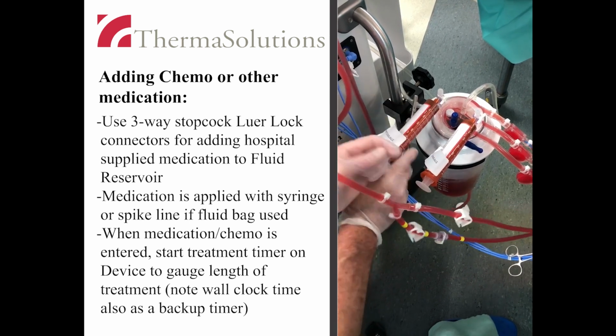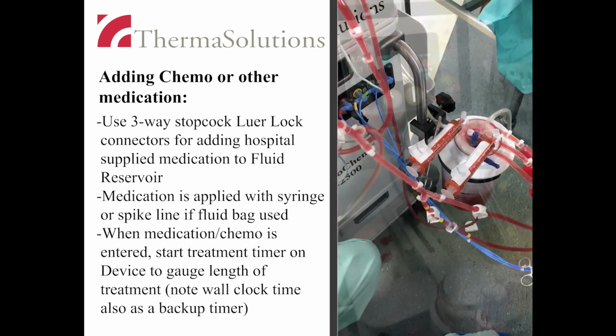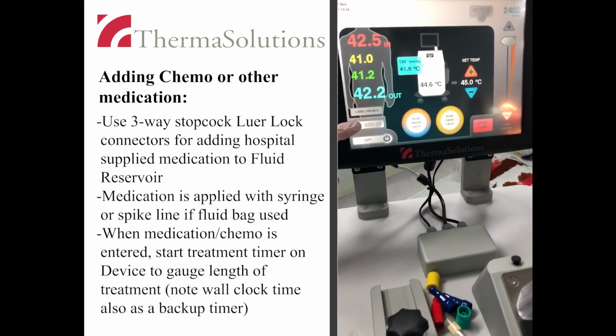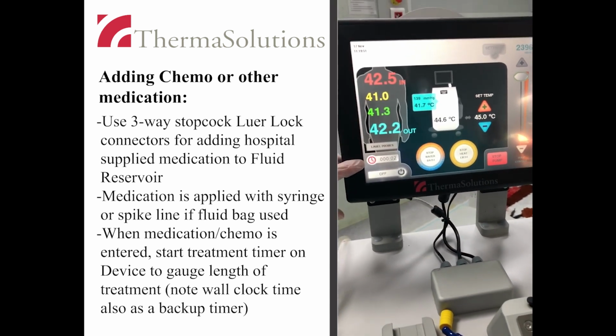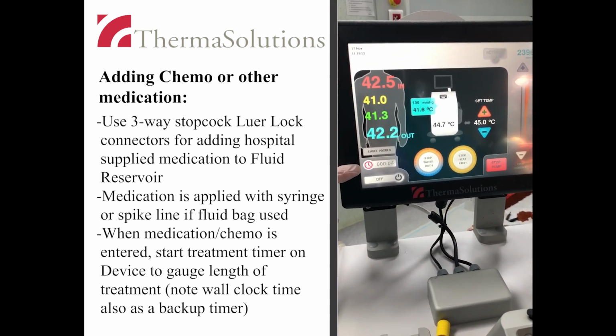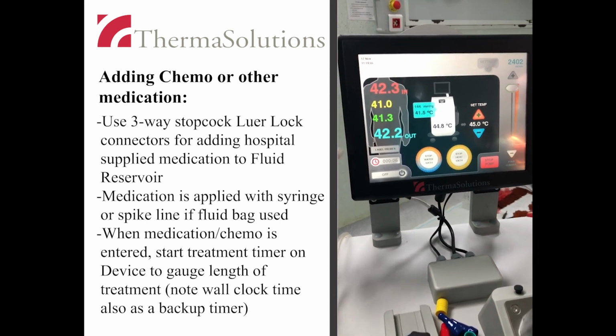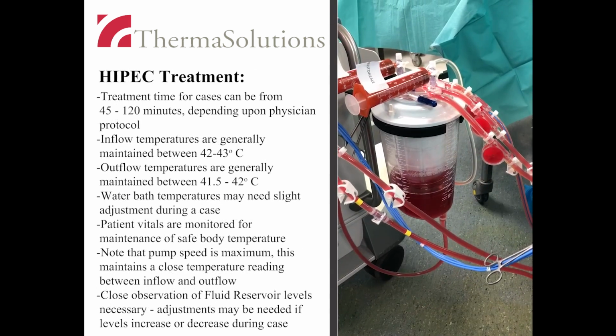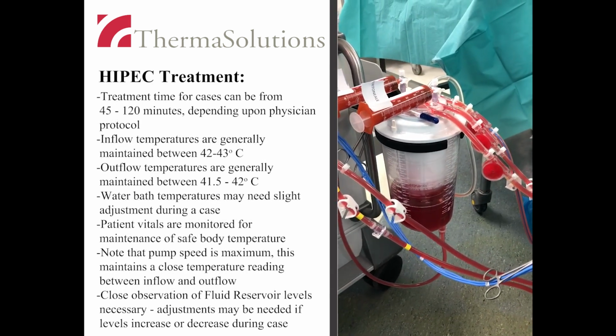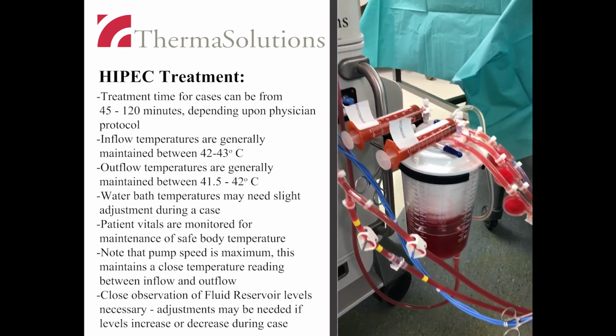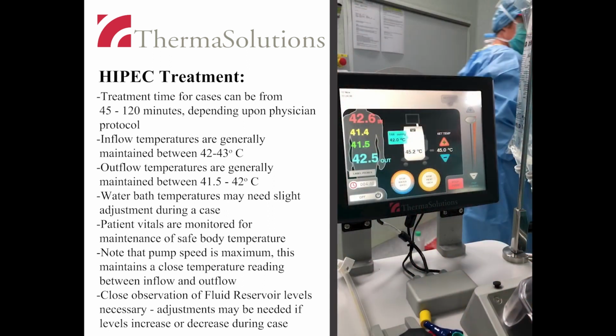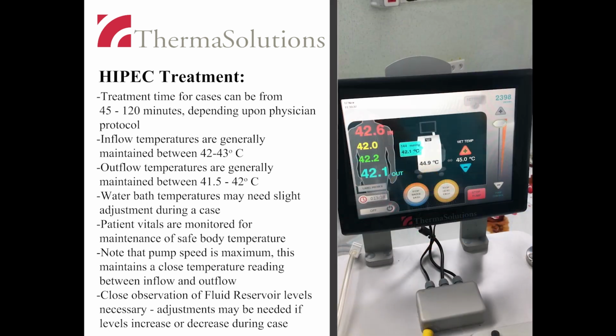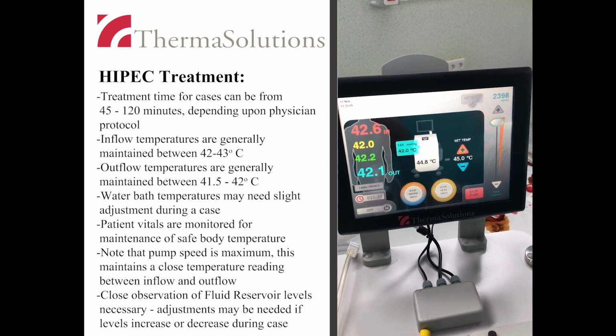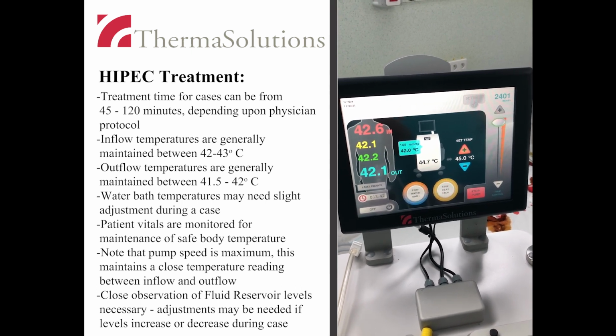After the medication or chemo is added, start the treatment timer by pressing the timer button on the home screen. A transcribed log or additional clock should be utilized as a backup method of timing. HIPEC treatment duration for cases can vary greatly depending upon the chosen protocol. Many published protocols indicate an inflow temperature between 42 to 43 degrees Celsius, with corresponding outflow temperatures generally between 41.5 to 42 degrees Celsius.